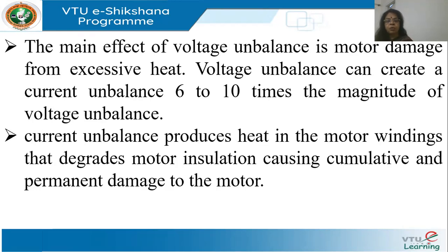Yes, there is a cause for concern. The main effect of voltage unbalance is the motor can get damaged from excessive heat. It can create a current unbalance of 6 to 10 times the magnitude of voltage unbalance. Large motors and equipment like generators are protected by what is called a negative sequence relay. Possibly you have studied it in your course on protection. This negative sequence relay will measure the line currents, compute the negative sequence component and trip the equipment when the negative sequence component is above a threshold. So we do not let the unbalance affect the motor. The motor is protected against severe unbalance.